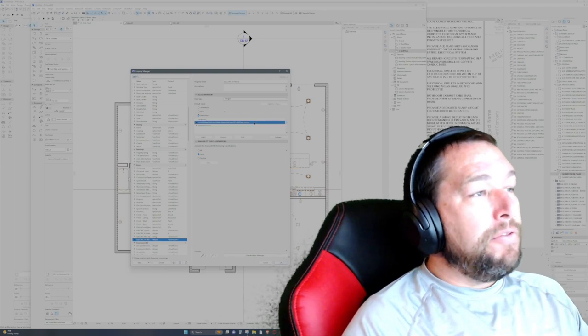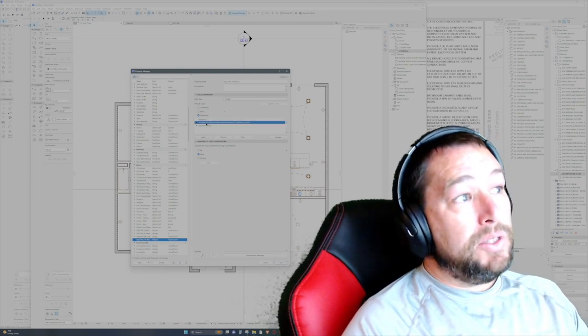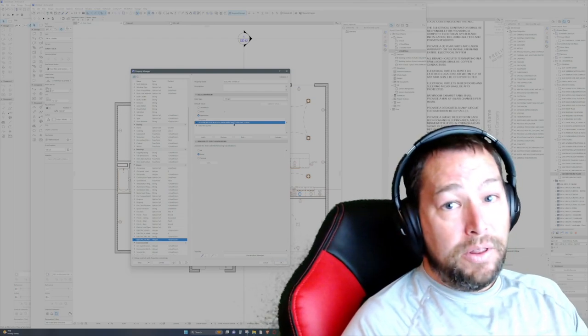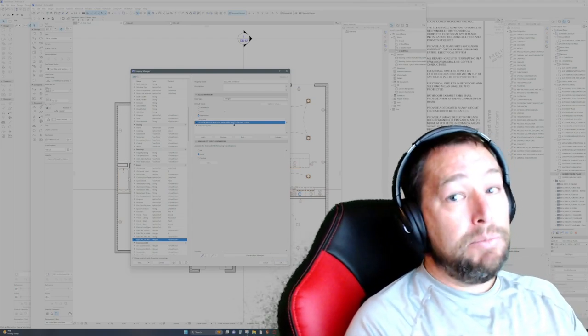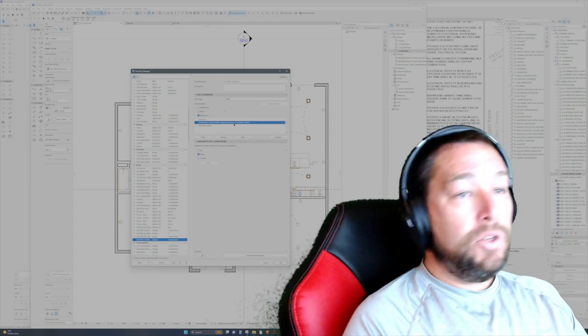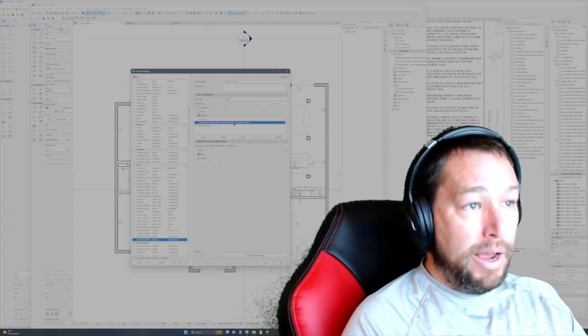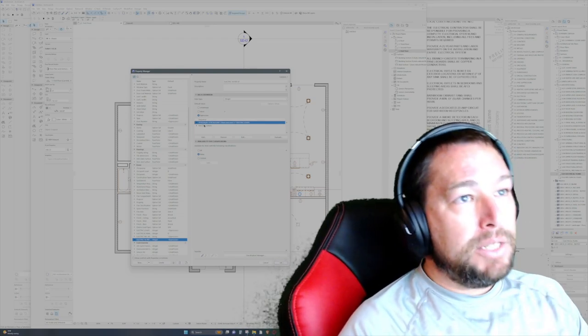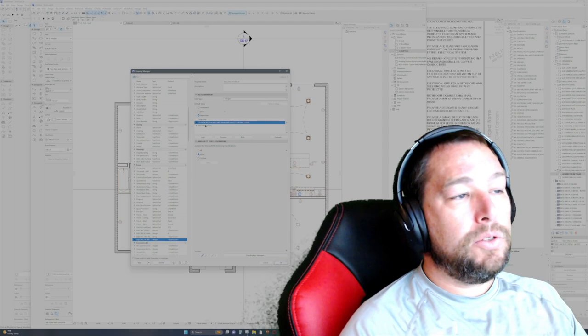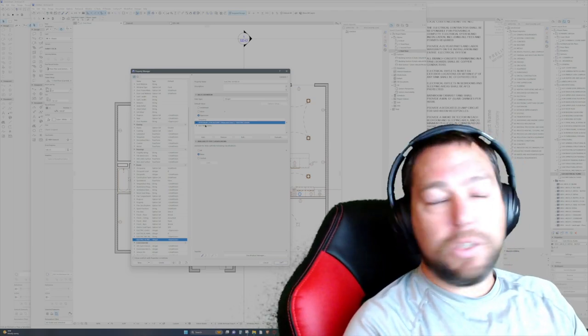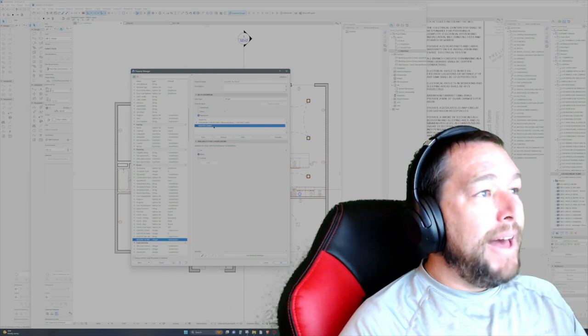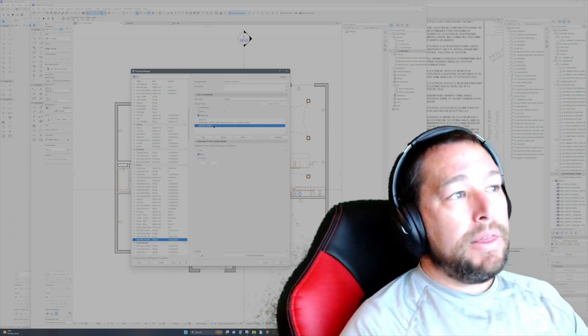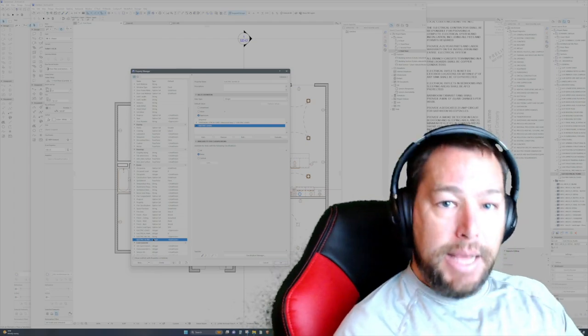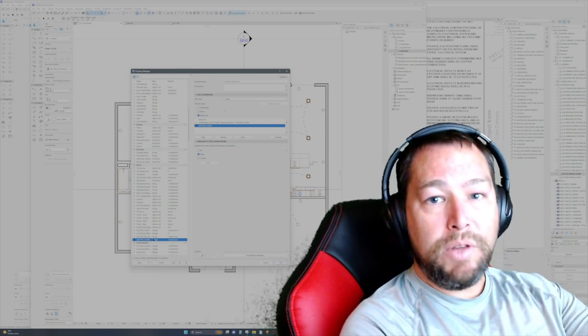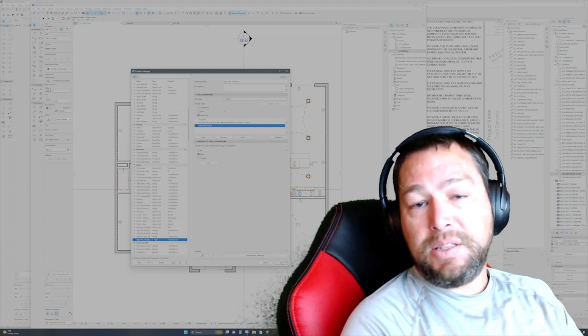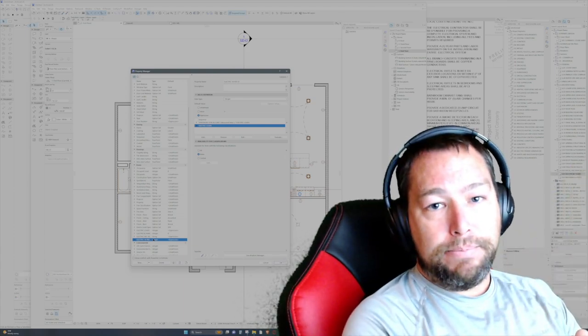Now, the first expression in the sequence is the one that calculates the measured area of the zone times the 3 volt amperes into the number of volt amperes for the entire house. For those objects that are not zones, that have no square footage—I'm talking the electrical outlets or dishwasher, refrigerator, all that stuff—then that is going to be covered by the electric loads. And what this whole property does is take those two different numbers, those two different columns in the schedule, and make them one column.